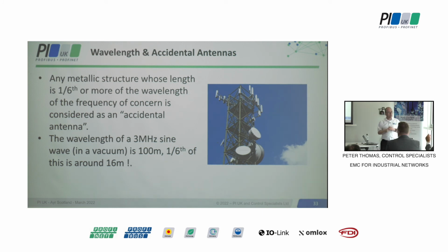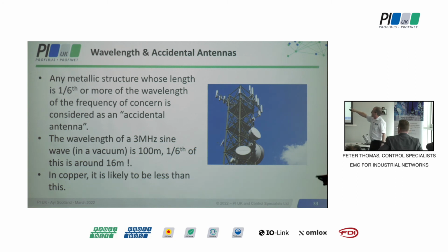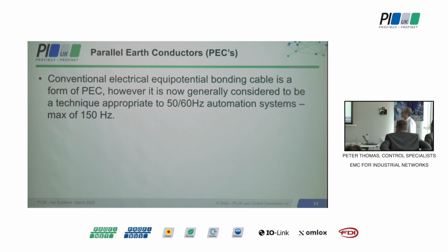Does your earth bonding account for that? Yeah, add that 16 meters on. Yeah, it's metalwork - a length of cable tray, vertical struts. It could potentially emit around the building. I just worked that out based on a vacuum with copper; it's going to be slightly less than that. So conventional equipotential bonding cable is a form of what's called a parallel earth conductor.